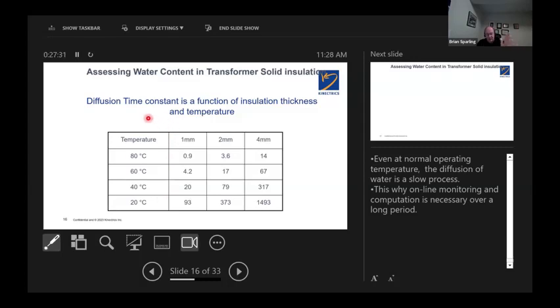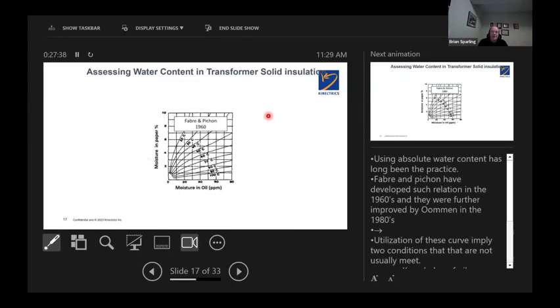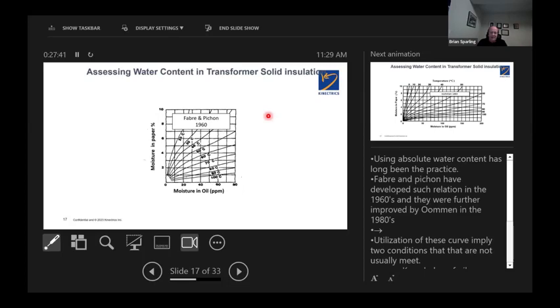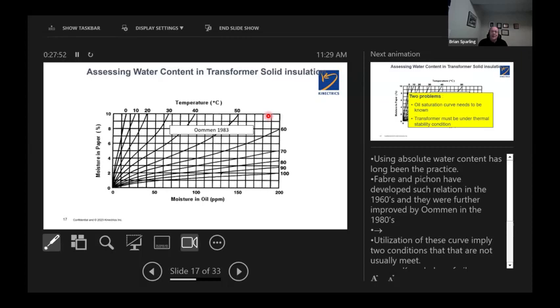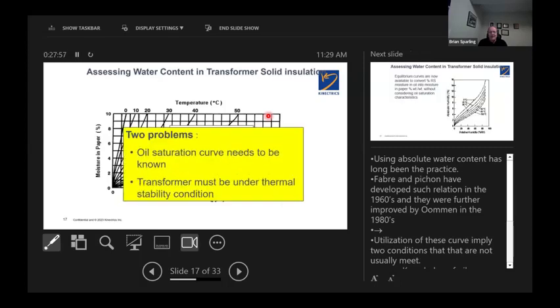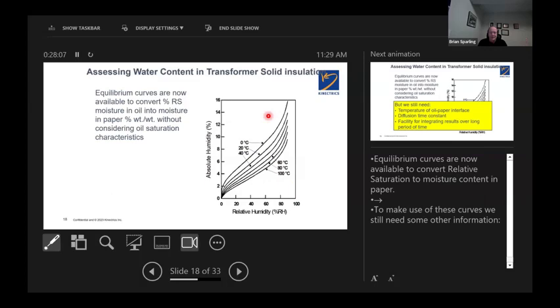And that's when we talk about online monitoring, which Chris was on the breaker side. From the transformer side, we take this into account to calculate the total aging rate. So over time, people have done this work of taking ppm and translating it into moisture in paper. Fabre-Pichon from the 1960s was the first attempt. Oommen tried to update that in 1983. The thing is, we don't know the saturation curve. We'd have to know the saturation curve, and the transformer must be in a more or less thermal stability condition, which unfortunately never really happens.